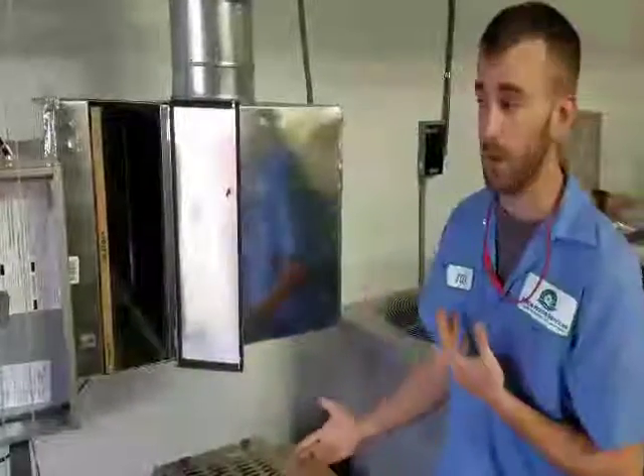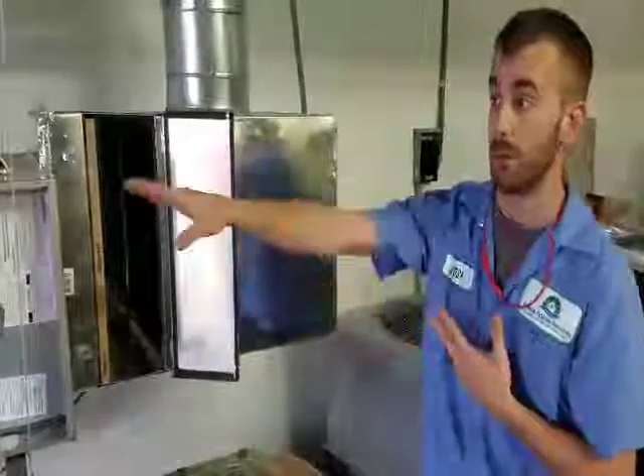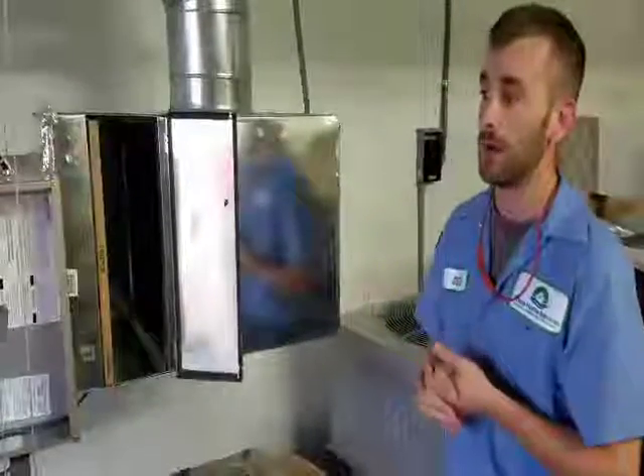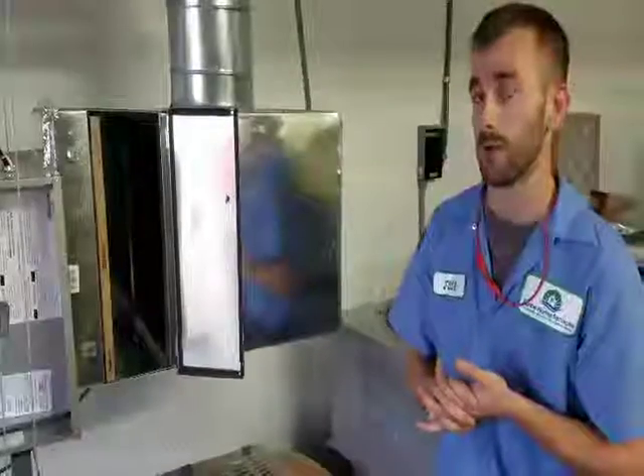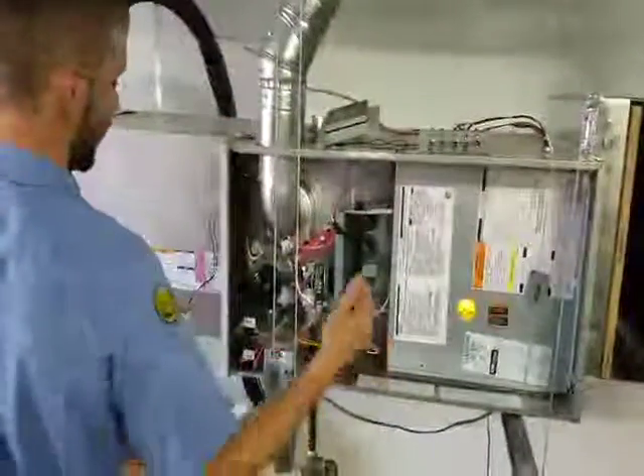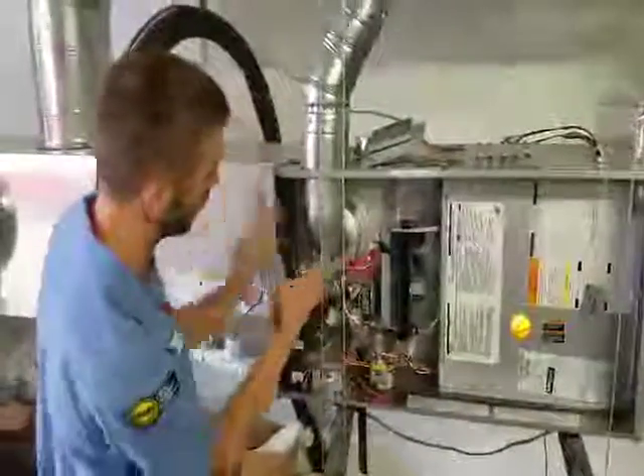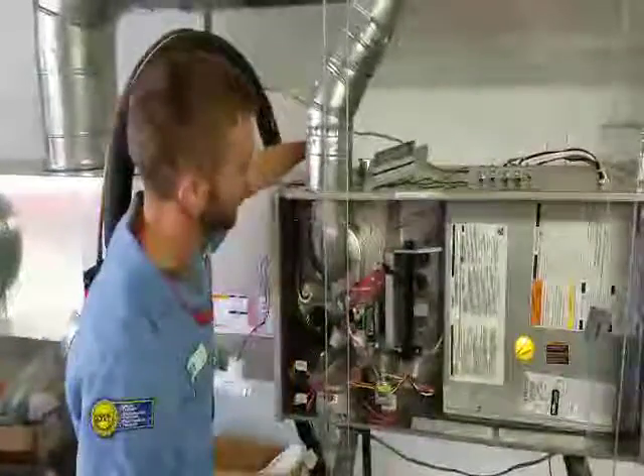Check for any carbon monoxide reading when a technician is going to do a fall tune-up. If you have a carbon monoxide reading on your supply side, which would be your main distribution box, you very likely have a crack somewhere. Right here is where your blower motor is going to be, and this is where your gas chamber is, and your heat exchanger is actually on the inside behind this flue pipe.